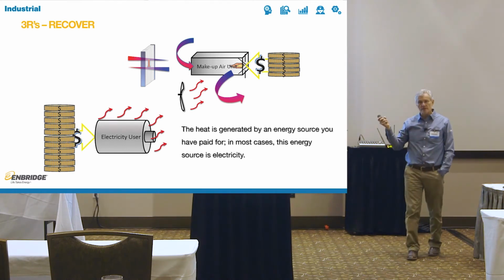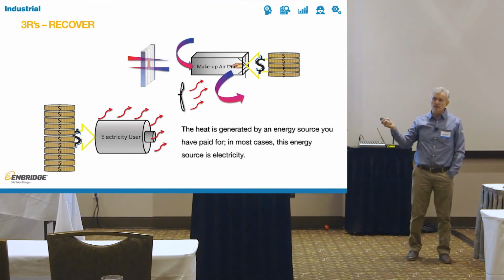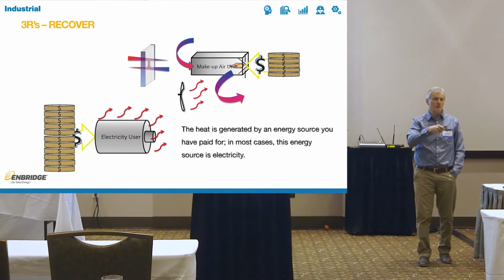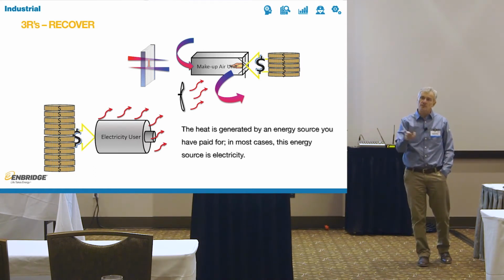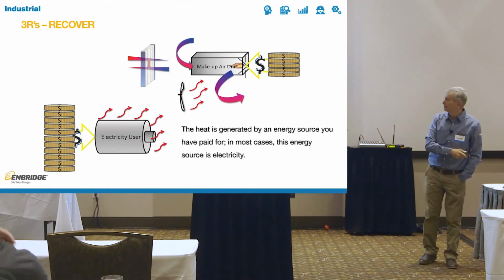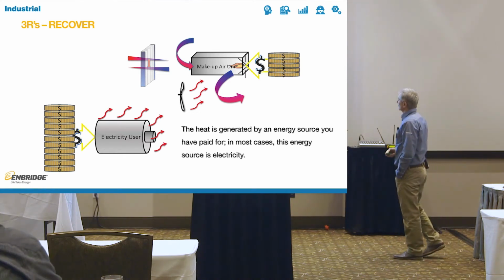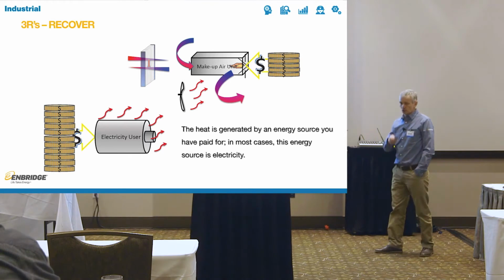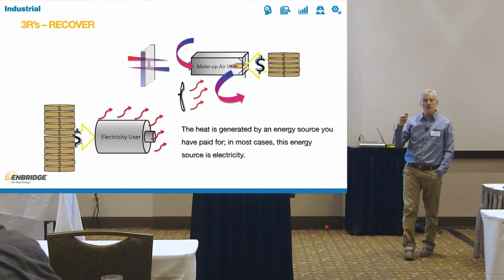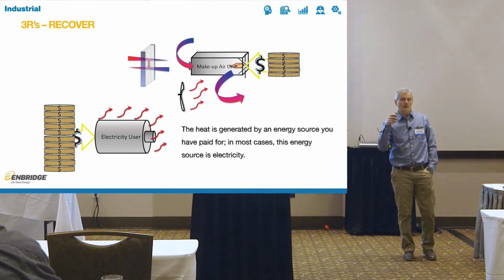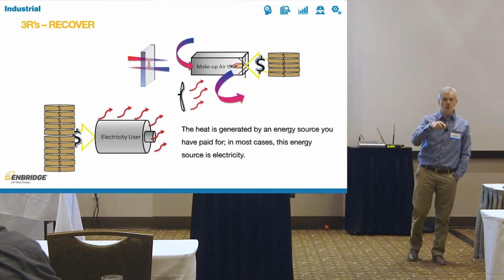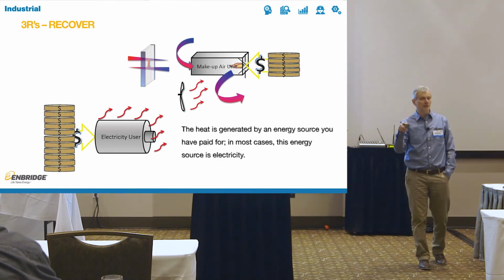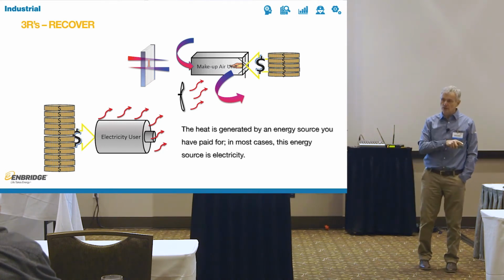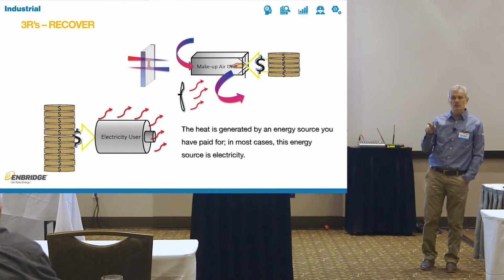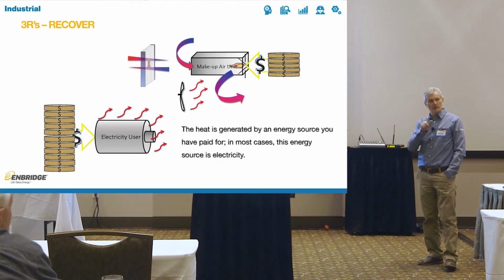And you have to remember, electricity is not free. This heat that every electricity user uses is not free. You paid for that electricity. It just happens to turn into heat. So let's look at the air-cooled air compressor project. We talked about it before. 80% of all the energy, so if you have a 100 horsepower compressor that you're so proud of, 80 horsepower of that is heat. You get no use of it. It just needs that heat to turn regular air into compressed air.